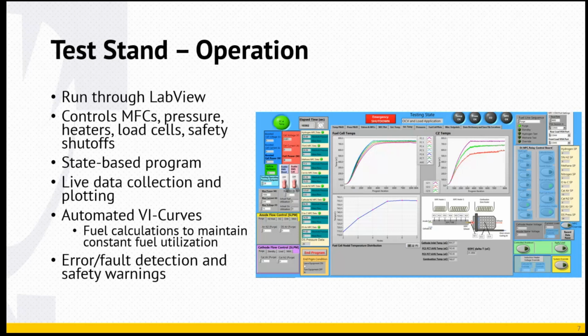This program also has error and fault detection built in. It's hooked up to some safety sensors and safety shutoffs with the gases as well. Some of the main ones: it won't let you run hydrogen below 500 degrees Celsius, and it'll warn you if it tries to flow a fuel but isn't actually flowing, which usually means you just forgot to open the tank or turn a valve.